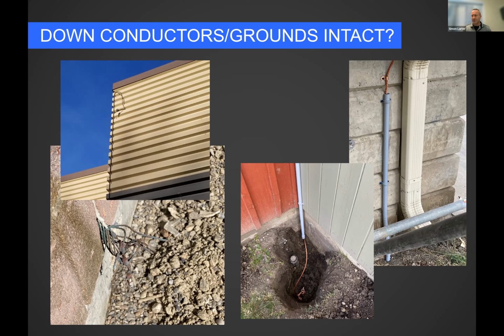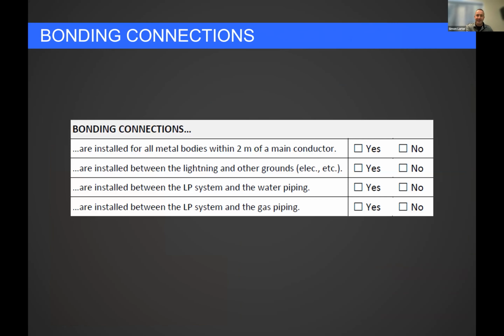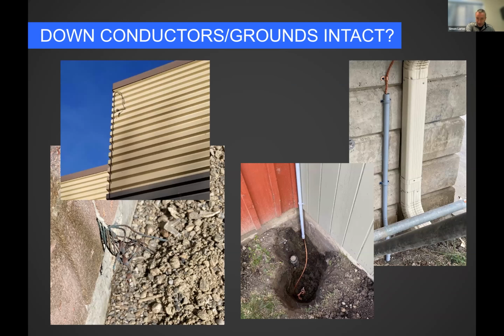The perimeter sidewalk had pulled away from the building and basically yanked the cabling right out, just snapped that copper cabling right there. So when we had to go back out and repair the grounds on that too, just double check, are the down conductors and grounds intact? Bonding connections.